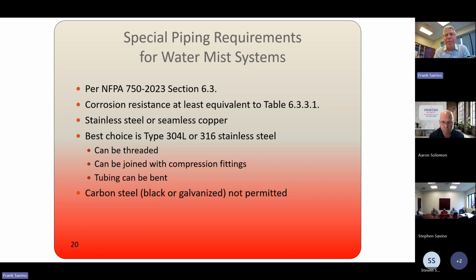So we designed the entire system for a light hazard occupancy with water mist. We were also able to use CPVC pipe, which was approved for this application because they had a hung ceiling and it was light hazard. So we did the job. Like Blaze Master? Yes, we used the Blaze Master, correct. We did the entire project with the Blaze Master pipe with water mist nozzles, and we got the 2-inch domestic to work. I should note, though, that they didn't have enough pressure to support the water mist system, so we did have to put in a fire pump.